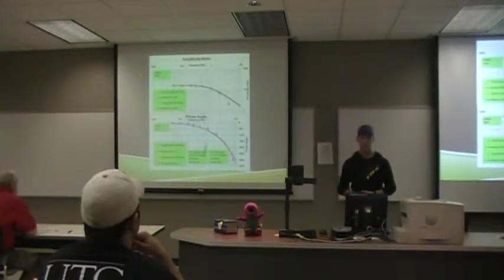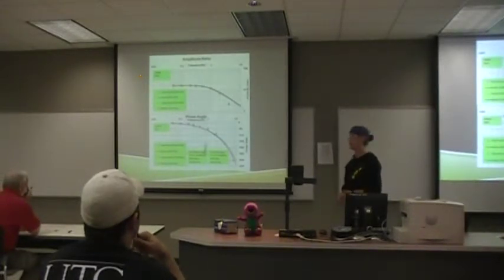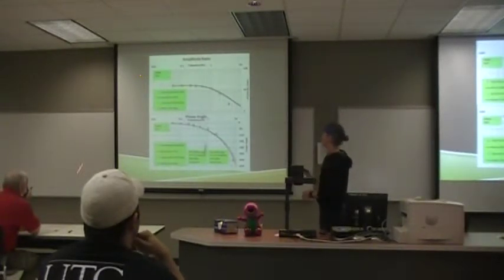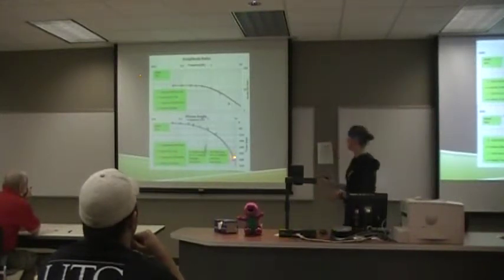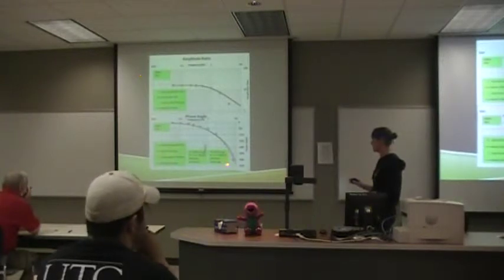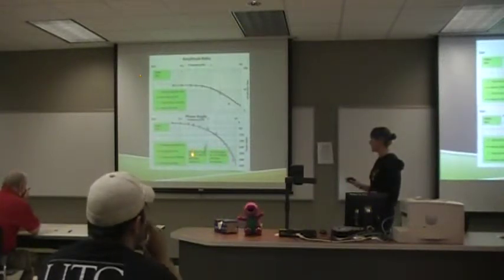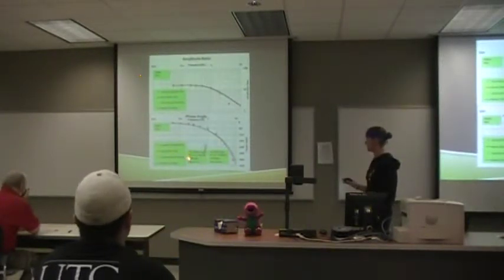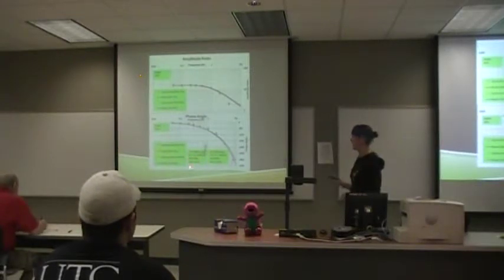This is another Bode plot, but this one has the model and experimental data on the same graph. The model are the lines, and the experimental data are the points. For the 50 to 75% range, K was 17.3, T naught was 0.09, and tau was 0.6. And for the 75 to 100% range, K was 17.1, T naught was 0.6, tau was 0.7.